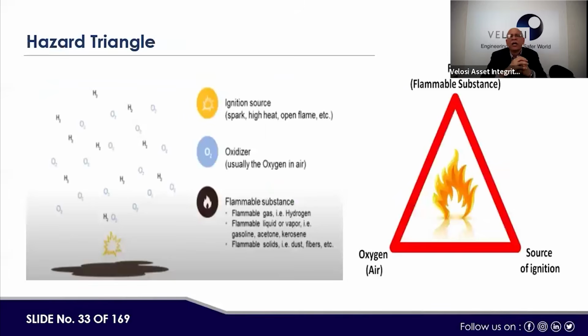Why? Normally, we know that there is a fire hazard triangle. In the fire hazard triangle, there are three things. Number one is a fuel or a flammable gas. Number two, oxygen, which is available in the air anyway. Then the third thing, which is missing, is the source of ignition. So the objective of HAC is that this triangle should not be established. If this triangle is established, then there might be a fire and explosion. And there is a lot of capital investment in these process plants. Secondly, there are people around, there is population around, and it may cause a disaster. So that's why, to eliminate one important angle of the fire triangle, we try to remove or control the sources of ignition.